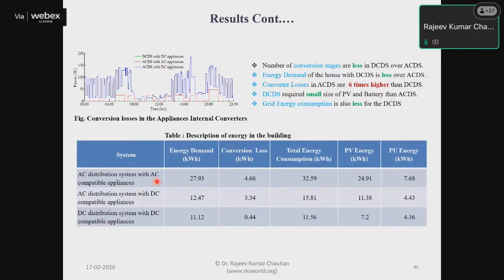In case of AC technology with AC distribution, 27.93 kilowatt hours is the energy demand for 24 hours. With the second case, it's 12. And with DC distribution system with DC technology, it's 11.12. Based on that, we can see the conversion loss is reduced significantly, about 10 times. The total energy demand of the house is reduced from 32 to 11, or around 33%, meaning only 1/3 of the power demand remains with DC technology.